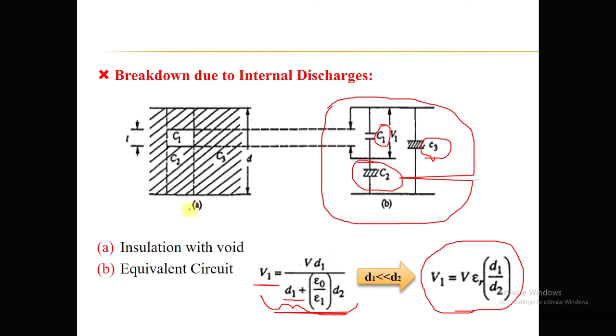Okay, so when you are performing the partial discharge test, you will see this kind of wave shape. V represents the applied input voltage, and as you can see, the applied voltage is sinusoidal in nature. As the voltage is increasing, the voltage across the cavity, this V1, also increases. Now suppose this is the limit at which the corona discharge breakdown of the cavity takes place. This Vi represents the inception voltage at which the breakdown of the cavity takes place.